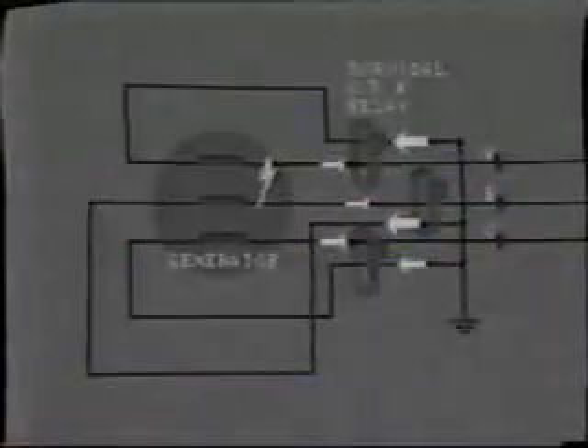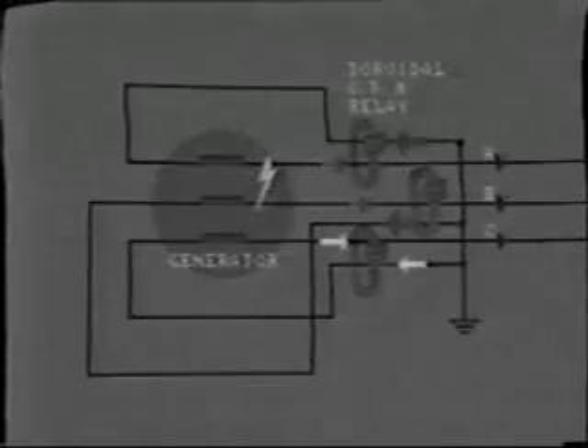When current flow is normal, the incoming and outgoing current balance out. However, in the case of an internal fault between phases, incoming and outgoing currents will not balance, and the residual will flow in the CT secondary and operate the relay. In this instance, the relay will usually be of the instantaneous overcurrent type.